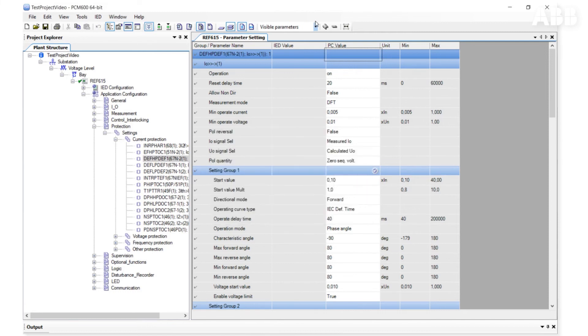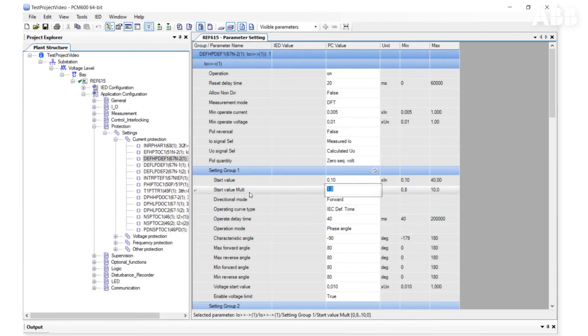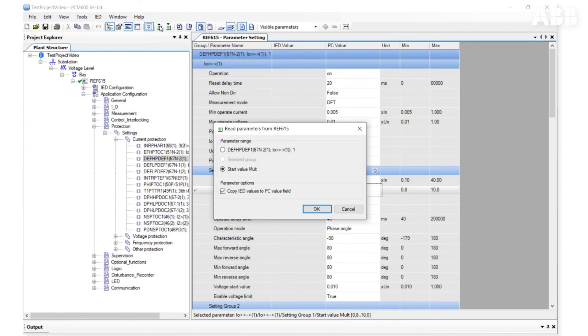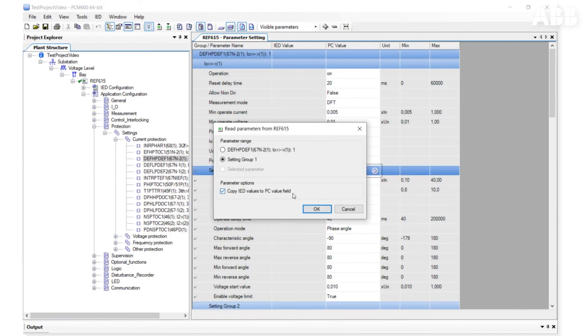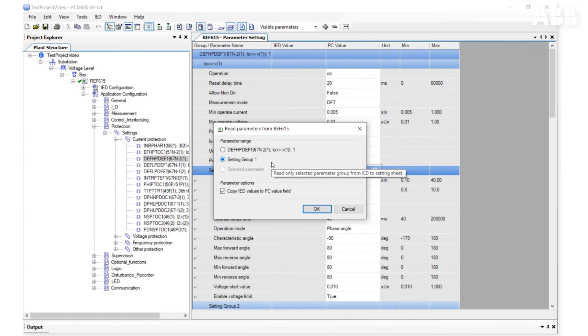There is another option – reading individual parameters or a group of parameters. If a parameter is selected, you can only read the selected parameter by clicking on it and clicking on the button Read Parameters from IED. You can do the same with a group of parameters. If you need to read all parameters from the relay, just select the relay from the plant structure and read them all.